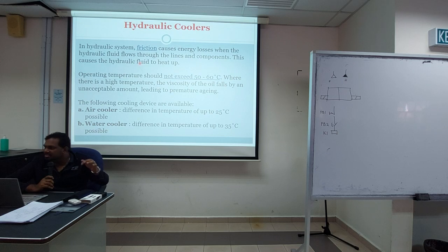Kalau dia lagi likat, lagi banyak friction lah. So it will cause the fluid to heat up. So it cannot be more than 50 to 60 degrees Celsius. Kalau lebih tu, dia akan energy akan loss lah daripada ni. So dia akan jadi not efficient. And it can cause the oil to undergo premature aging. Premature aging maksudnya, so let's say the hydraulic oil can be used for 4 months. Dalam 2 bulan dia dah tak boleh pakai dah. So you need to do servicing lagi. So it will cause a lot of problem lah.